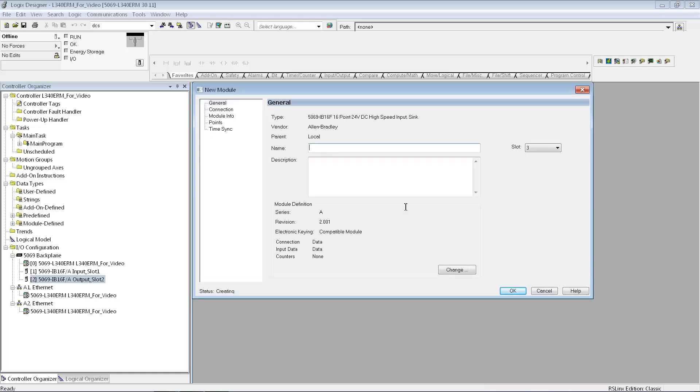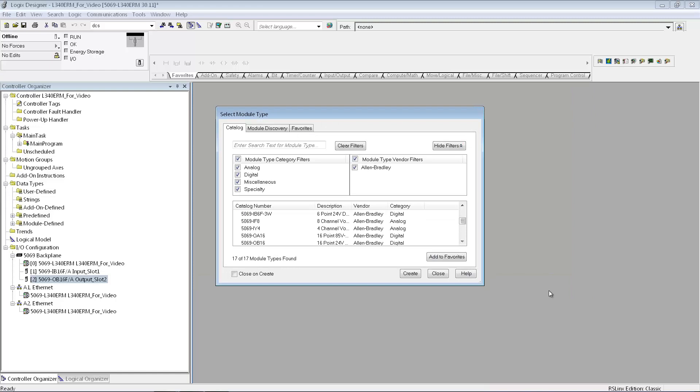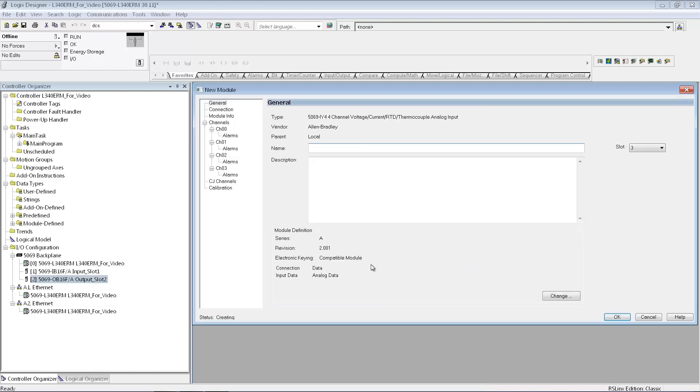I have a third module in my demo. The third module I have is a universal analog card, kind of a cool card because that one can be an RTD, a thermocouple, an analog in, a voltage analog in. You can configure each channel however you would like.